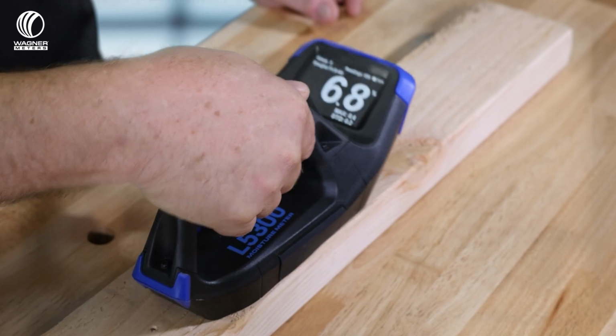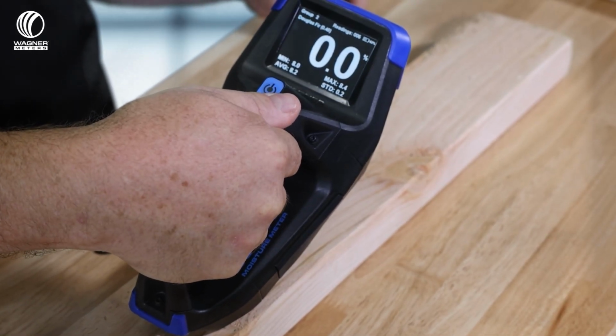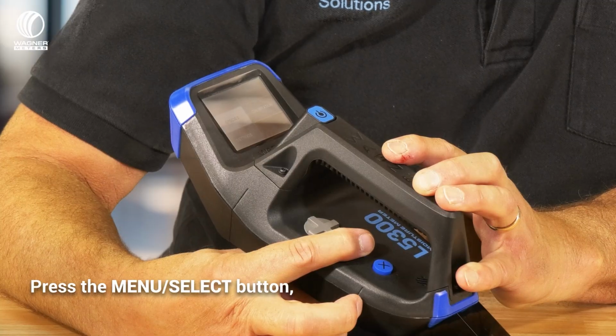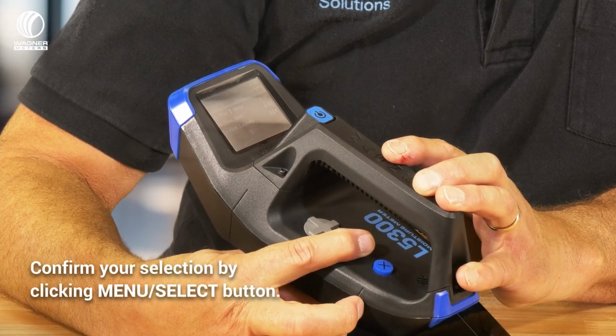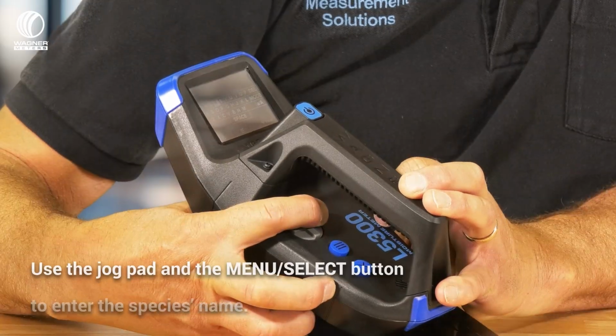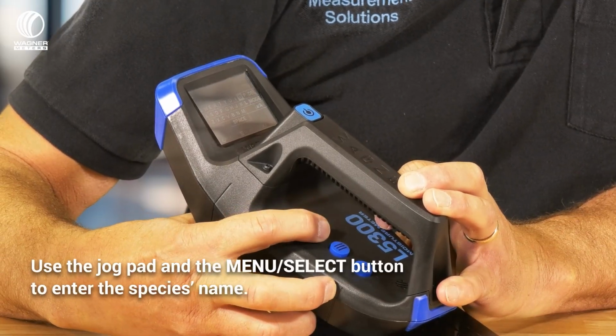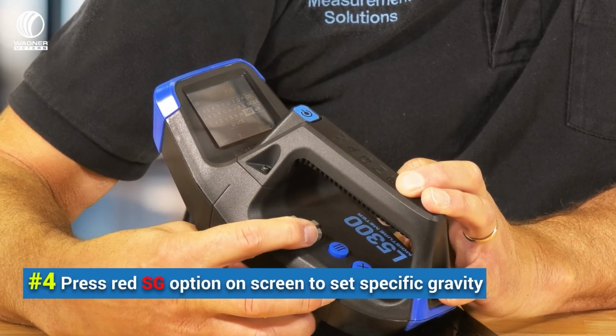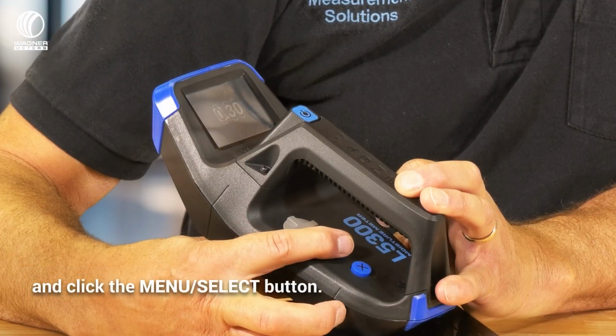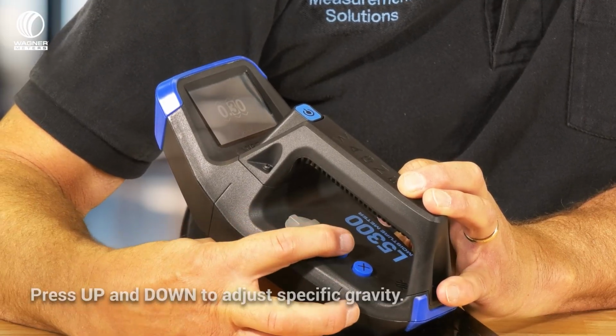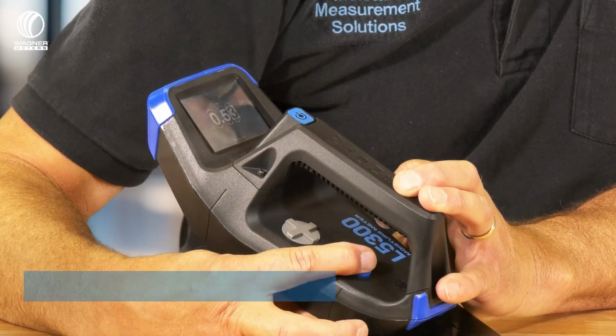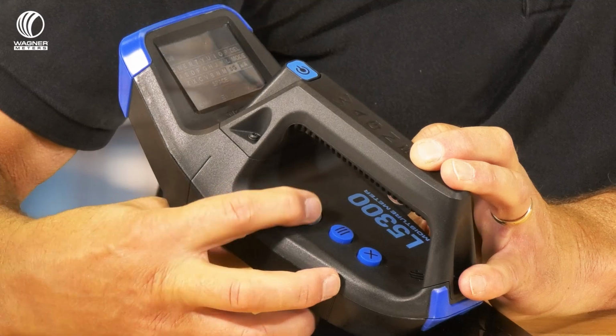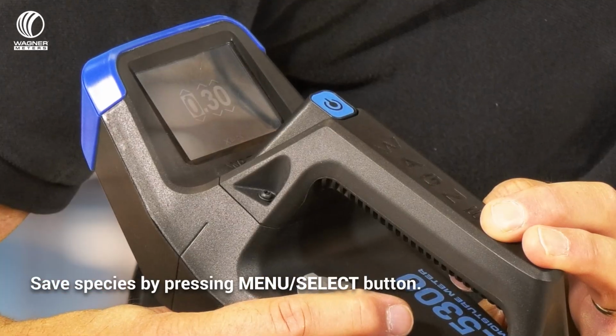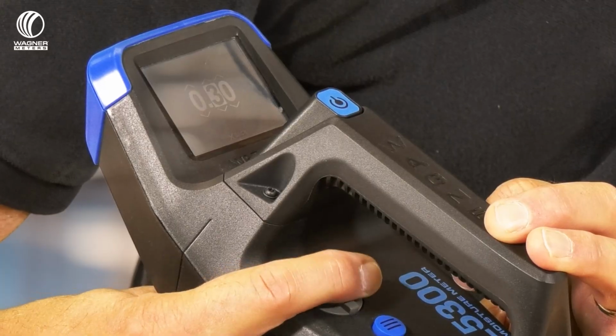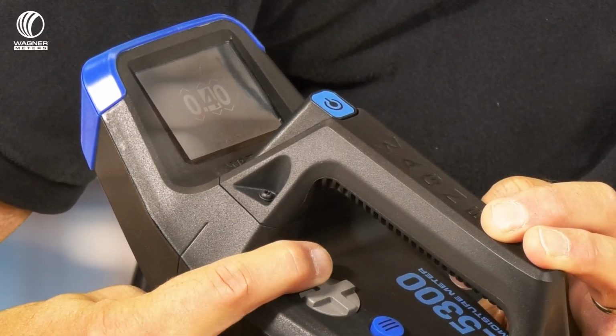You can customize your species list by adding or editing wood species. To add a new species, press the menu select button, navigate to the species menu, and confirm your selection by clicking the menu select button. Use the jog pad and the menu select button to enter the species name. To set the specific gravity, use the jog pad to navigate to the red SG option on the screen and click the menu select button. Adjust the specific gravity by pressing up and down on the jog pad. Once set, press the back button. To save your new species to the meter, press the menu select button.